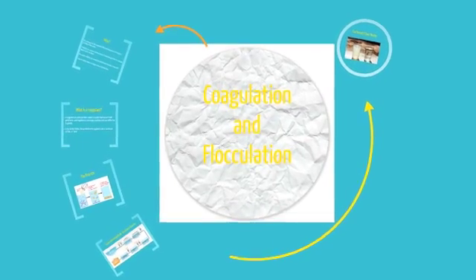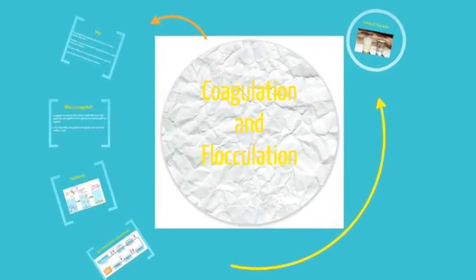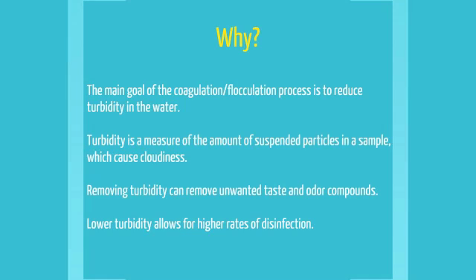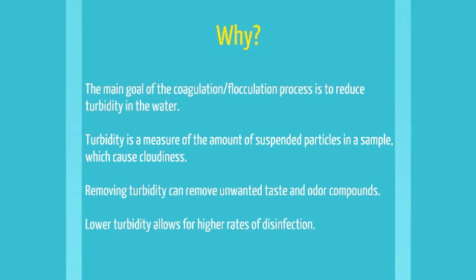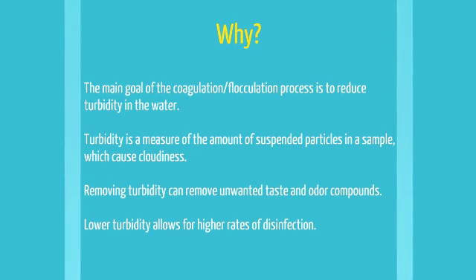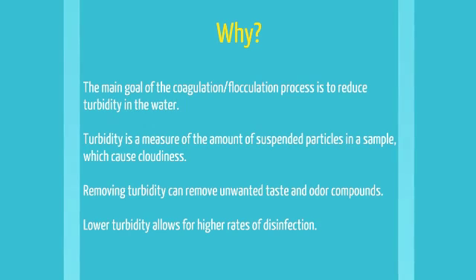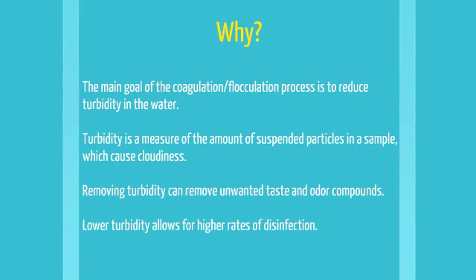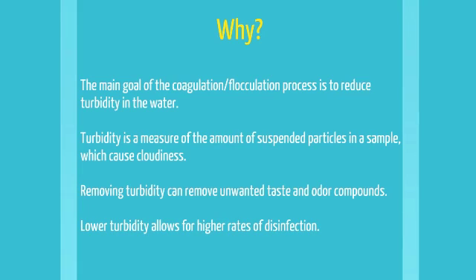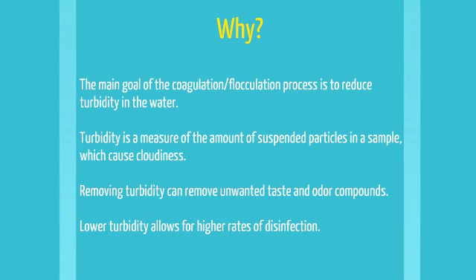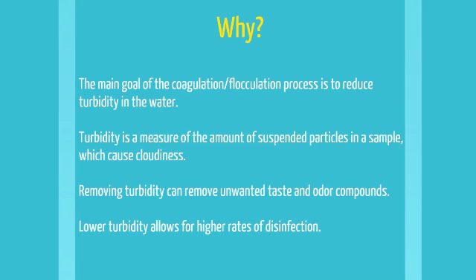Let's talk about coagulation and flocculation. The main goal of the coagulation flocculation process is to reduce the turbidity in the water. Turbidity is a measure of the amount of suspended solids in a sample, which causes cloudiness. Removing turbidity can remove unwanted taste and odor compounds. Lower turbidity allows for higher rates of disinfection.